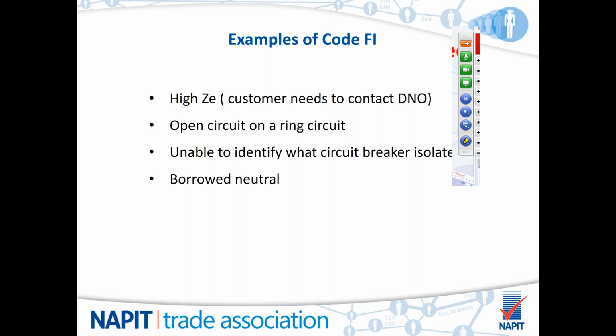So, a few examples of further investigation codes. As I say, further investigation is not new. They just got coded 1s, 2s, 3s, and in the old days 4s. So they're not new, but these days things like a high Ze, the incoming earth has got a high resistance. Not a lot you personally can do about it, but the customer could get in touch with the DNO, seeing if the TN-S system can be improved, moving on to a PME, TN-C-S system, whatever. There could be an open circuit on the ring. You're testing your ring, lines are okay, CPCs are okay, but you've got a break in the neutral.